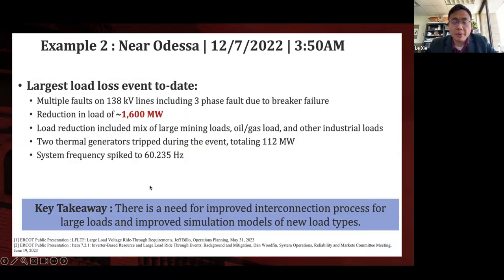There's another one that happened about a year ago, the largest load loss event to date. There were multiple faults on a 138 kV line, including a 3-phase fault due to breaker failure, that led to tripping of some 1.6 gigawatts of large loads, particularly computing loads, along with oil and gas and other industrial loads—but the biggest one was the computing loads.